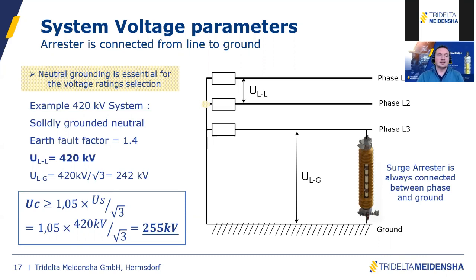So then comes the calculation for the UC, often called MCOV, for maximum continuous operating voltage, which is a term coming from the IEEE standards, but in IEC it's UC. So we use a 5% safety margin coming from disturbances and harmonics to define the minimum MCOV or UC that you need to use for the surge arresters. In that case, it is 255 kV.